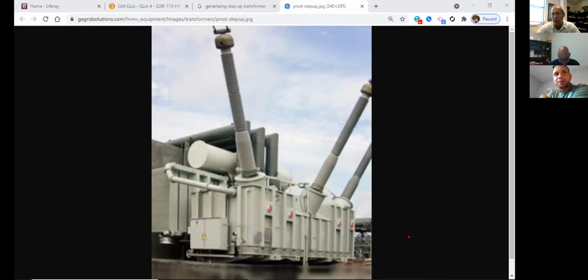It is. Okay, so this is what they call a step up transformer. We learned before that if we hooked up a generator to a normal transformer on the 240 side, we get 7,200 volts out the top. Well, that's what they're doing here at a generating station. What I really want to discuss here is this is the output, this is my high voltage out, this is my low voltage in. Do you see the size and diameter of these pipes that are coming into the transformer? Yeah. All right, so really one thing I've got to use here is a very, very large conductor.